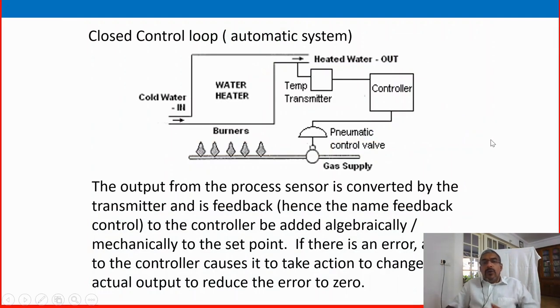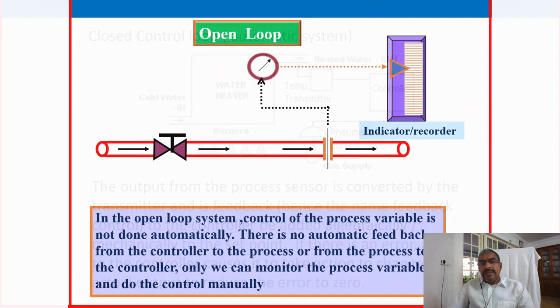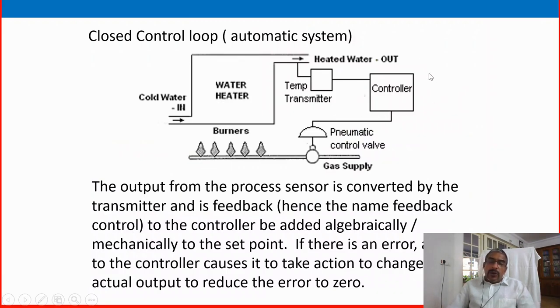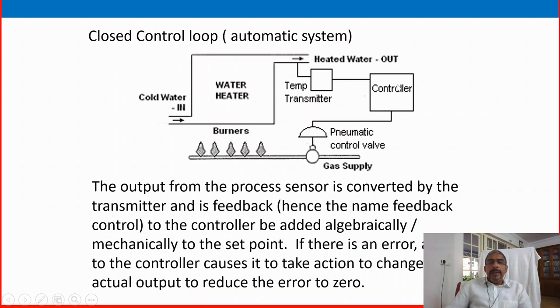In a closed control loop, compared to the previous open loop example where an operator was standing by, we have removed the operator and put an electronic or pneumatic controller — the rest of the things remain the same. The output from the process sensor is converted by the transmitter and fed back — hence the name feedback control — added algebraically or mechanically to the set point. If there is an error, the signal to the controller causes it to take action to change the actual output to reduce the error to zero. The controller compares the set point with the current process variable value coming from the temperature transmitter, and the output is sent to the control valve to maintain the water heater temperature at the desired value.